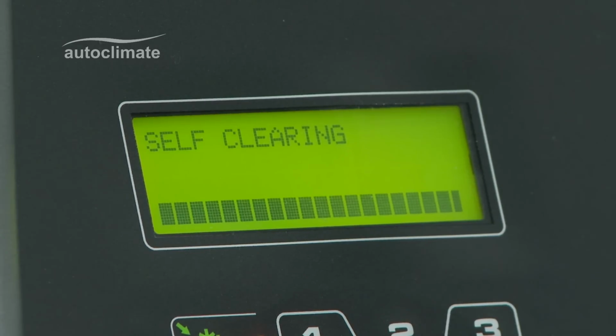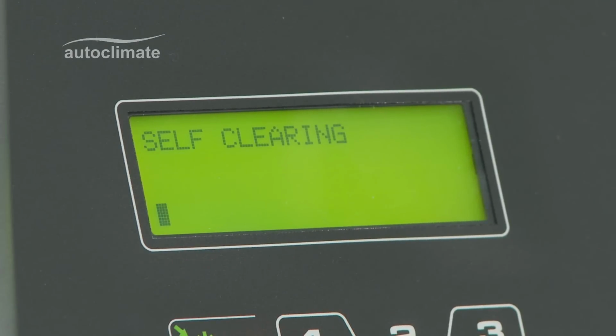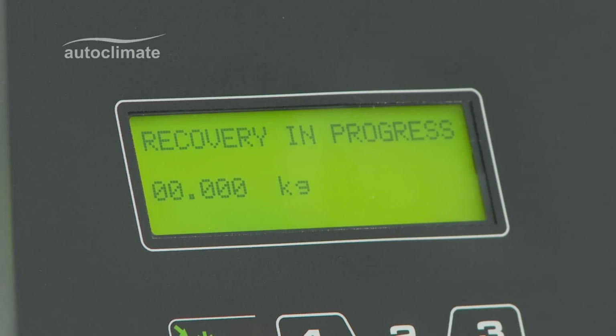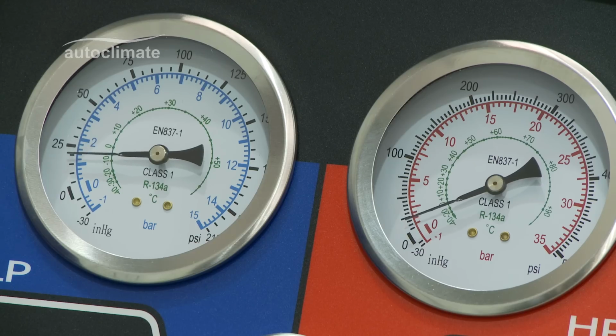The display indicates self-clearing. This process, which takes around 3 minutes, clears the machine to make the recovery more accurate. When complete, there is an audible click and the screen display changes to recovery in progress and shows 0 kilograms. The recovered amount showing on the display increases and the high and low side pressures move to zero.